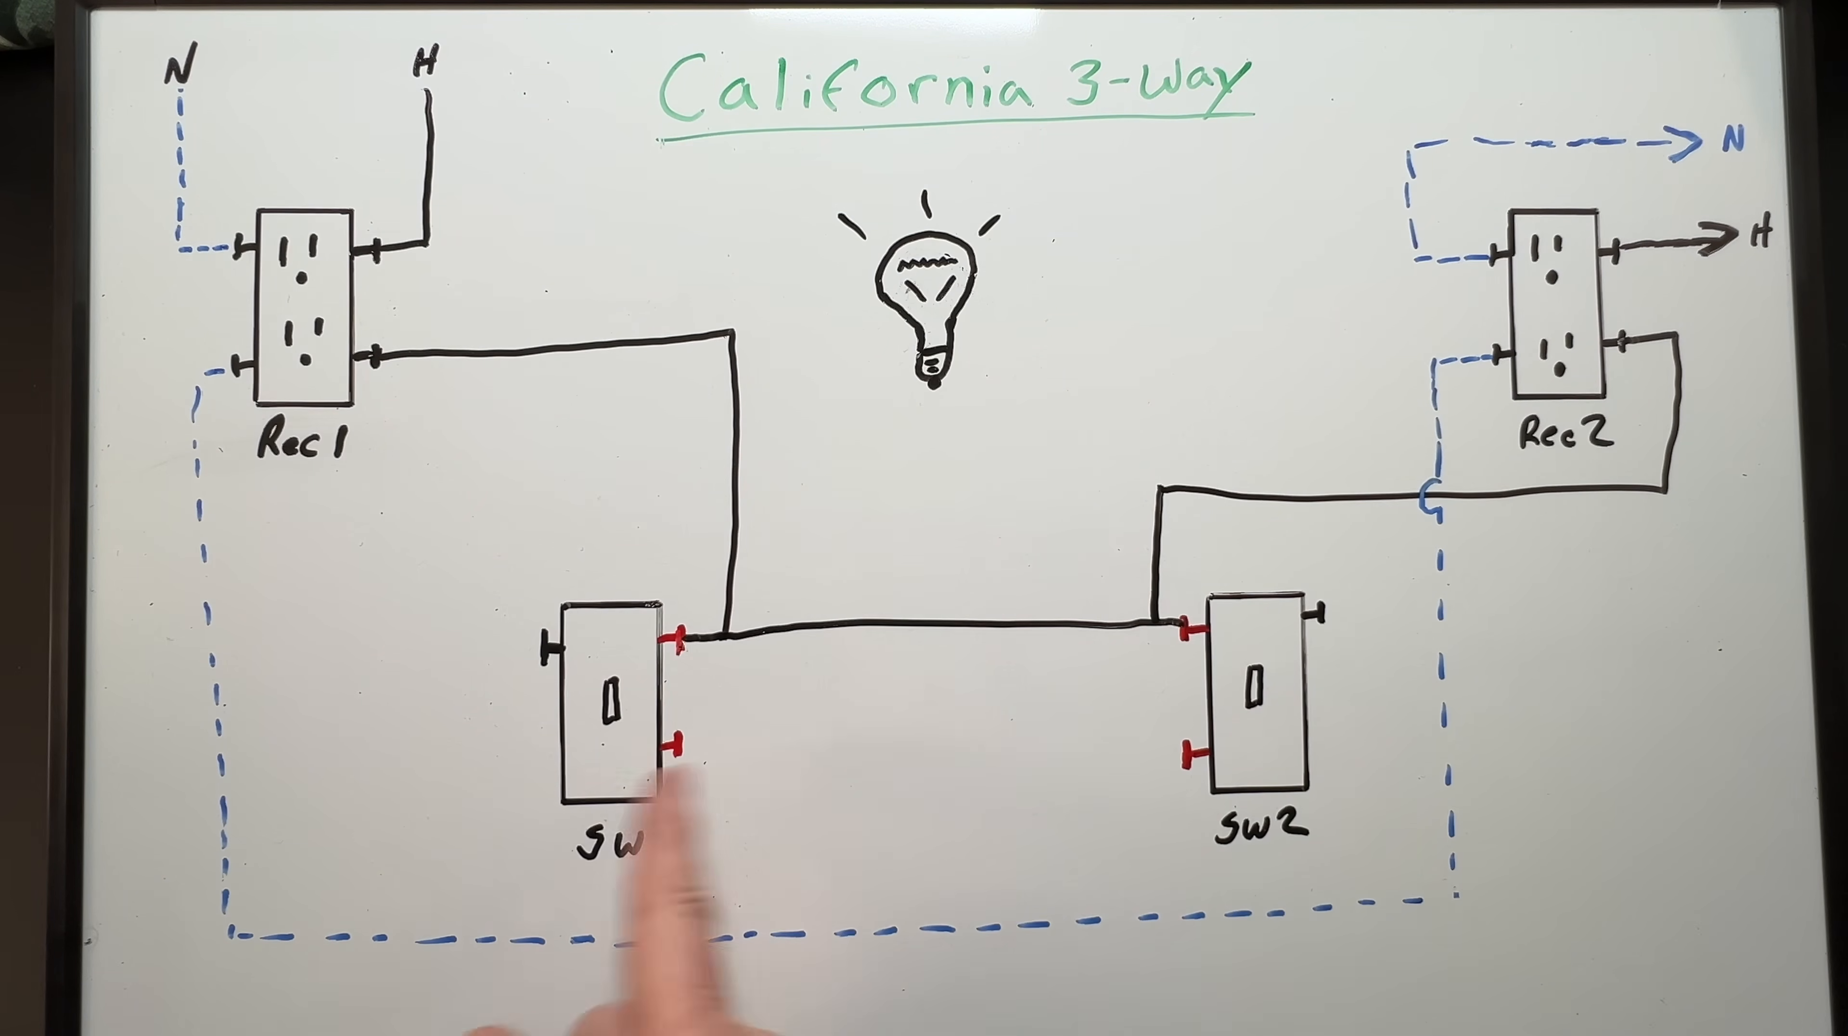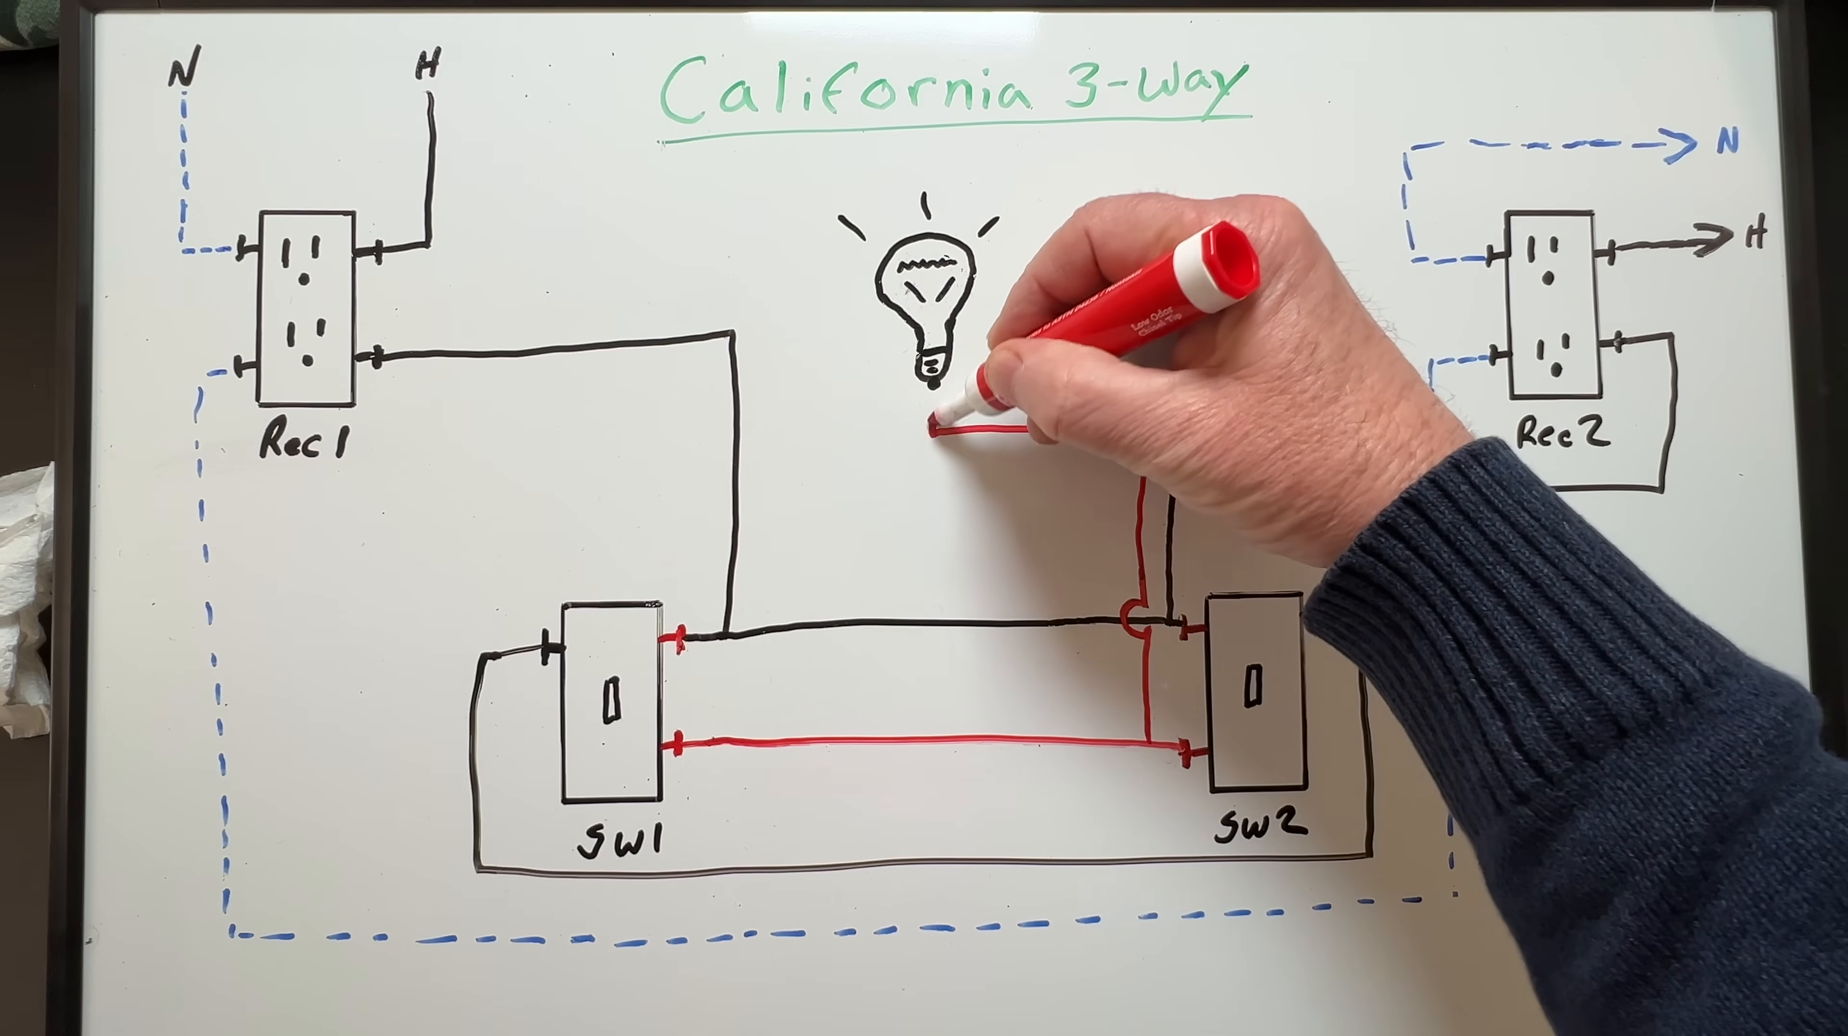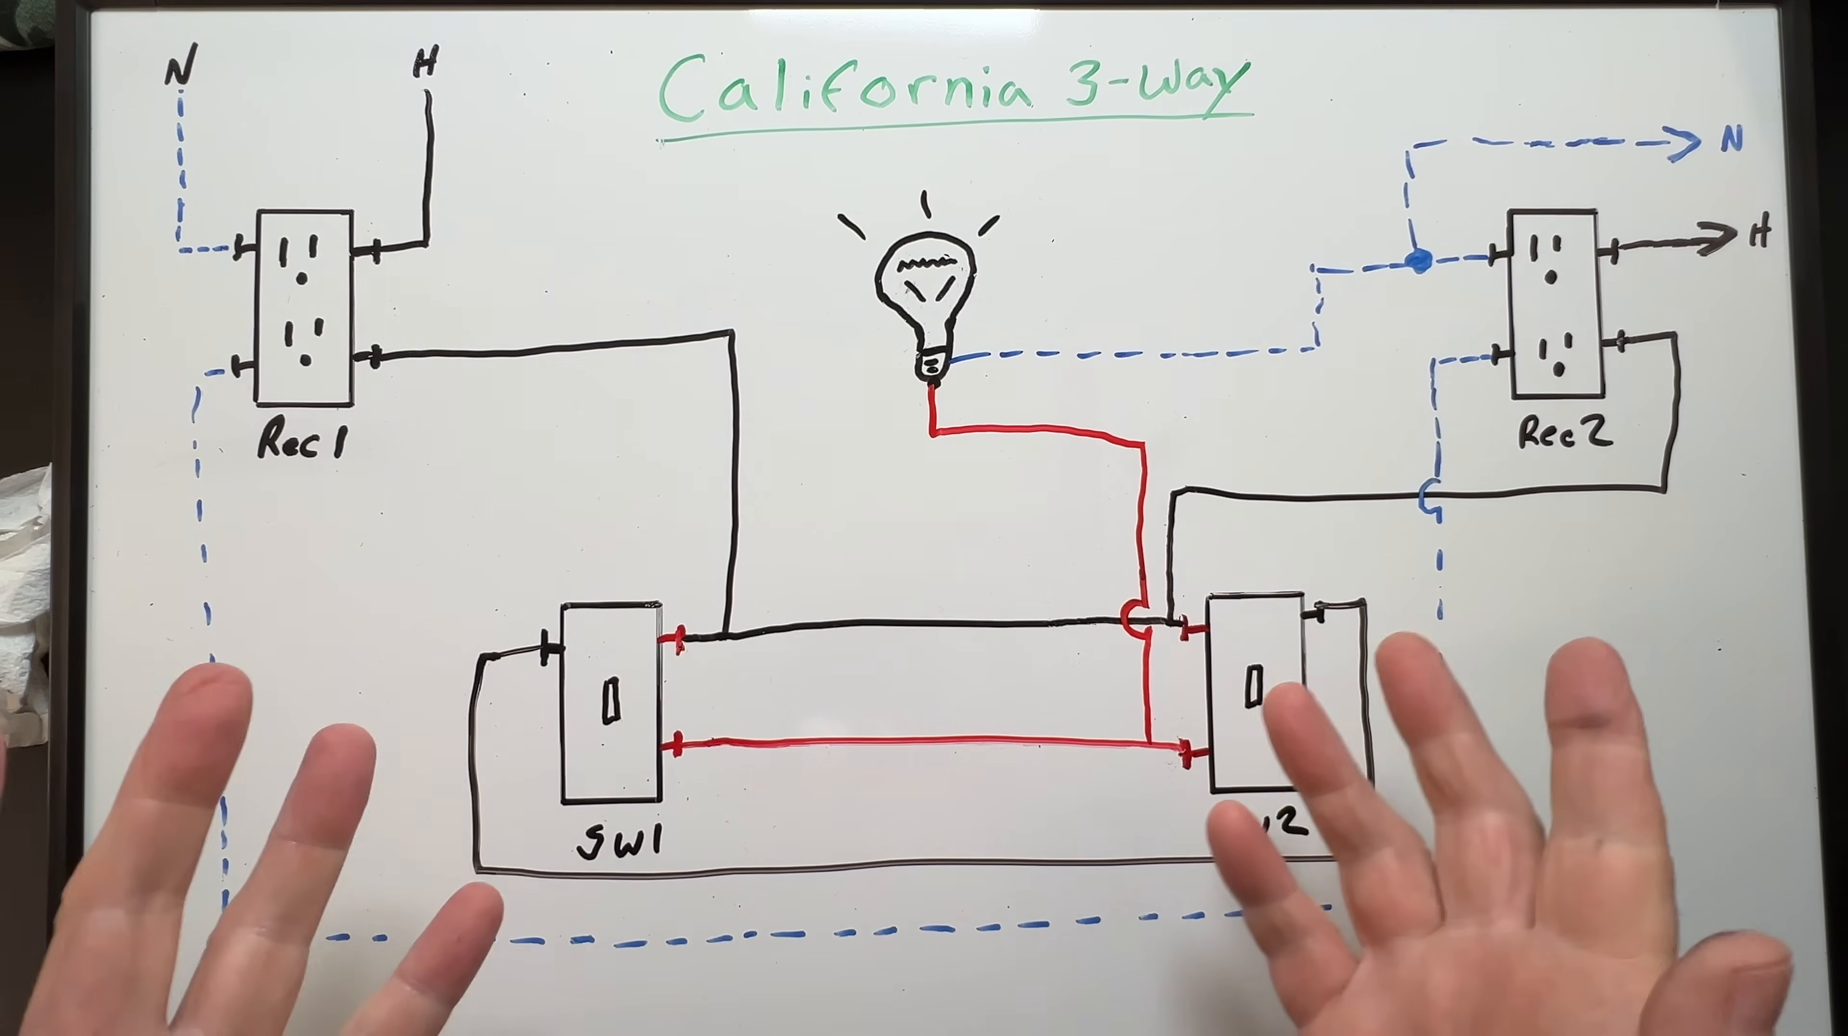Now we need to connect our light switches and our light. We'll take a red wire from the traveler screw on switch one over to the traveler screw on switch two. Now we're going to take a black wire from our common screw on switch one across to the common screw on switch two. Bear with me, this is all going to make sense in a minute. Next, we'll take a red switch leg wire from our traveler screw on switch two up to the black hot lead on our light. Then our white neutral wire will extend from receptacle two over to the white lead on our light. And of course, each location will have ground wires as well. And that's it. Our wiring is done.